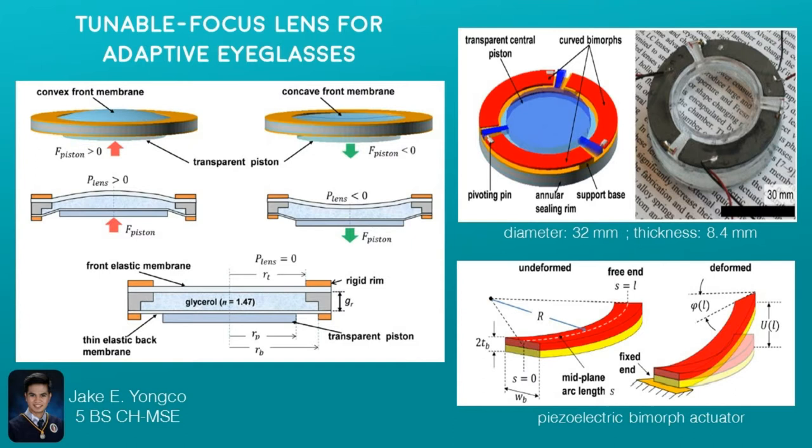When the piston moves, the shape of the upper membrane changes and it can form a convex or concave lens. In order to move the piston, they attach it to piezoelectric bimorph actuators. These piezoelectric actuators bend if voltage is applied, but since they are curved — meaning the inner radius is less than the outer radius — they can actually tilt inward or outward. Since the piston is pinned to the bimorph actuators, the piston can be moved through this mechanism by just adjusting the voltage applied to the bimorph actuators.